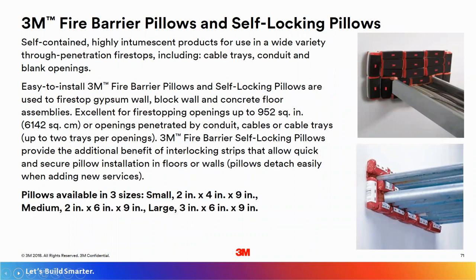The next product I'm going to show you here is the pillows. These are fire barrier pillows. So it is an intumescent wafer that is shrouded in a plastic overwrap. The materials get left in the plastic overwrap and installed in the opening. We have 2 versions of this product, one of them with just a plain plastic wrap, and we have another one that has Velcro, so you can secure the pillows together. This is a pretty quick way to close down a large opening. Can be used with cable trays and conduit, and we have them in a few different sizes. We have them small, medium, and large.